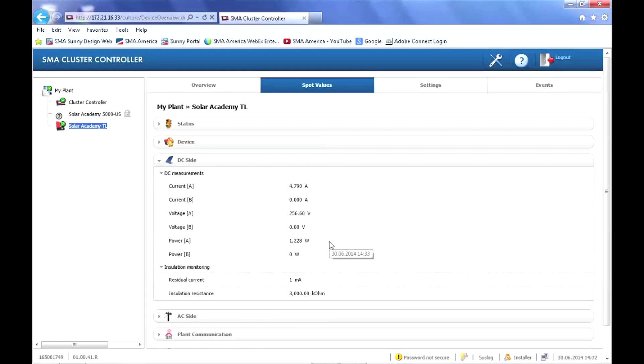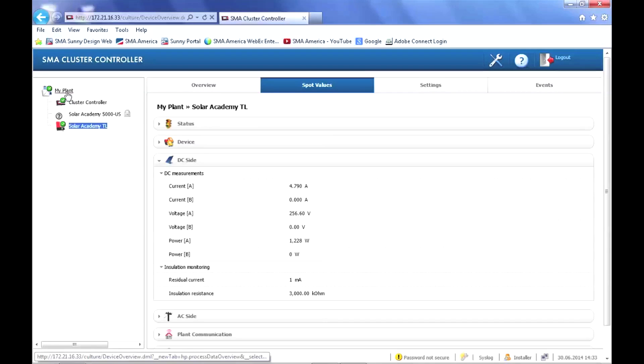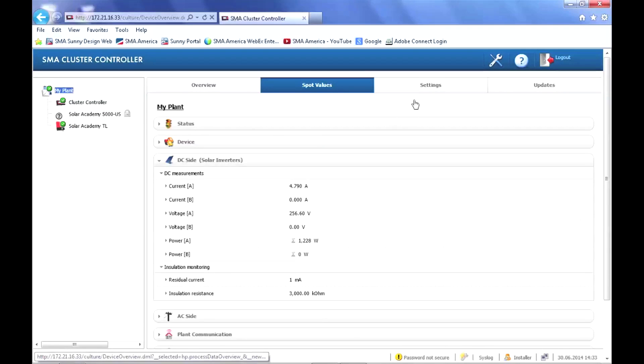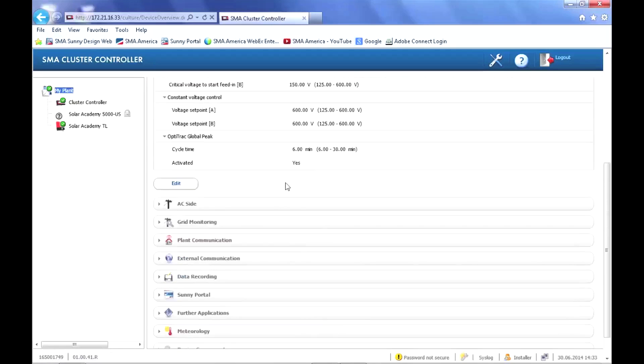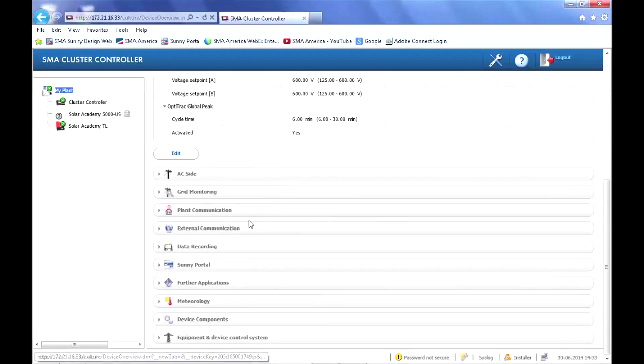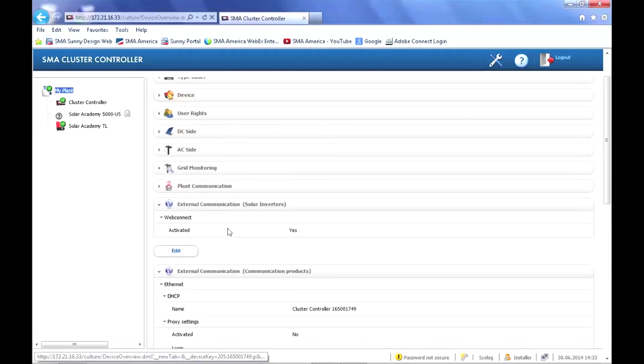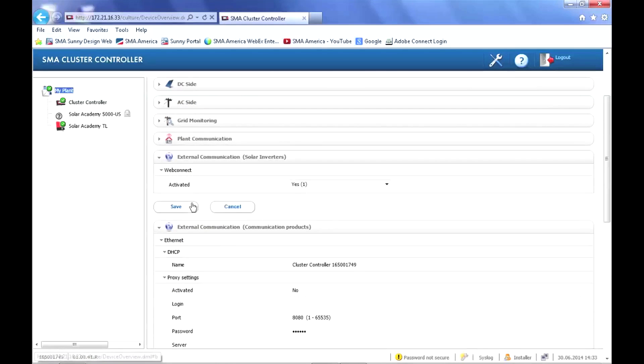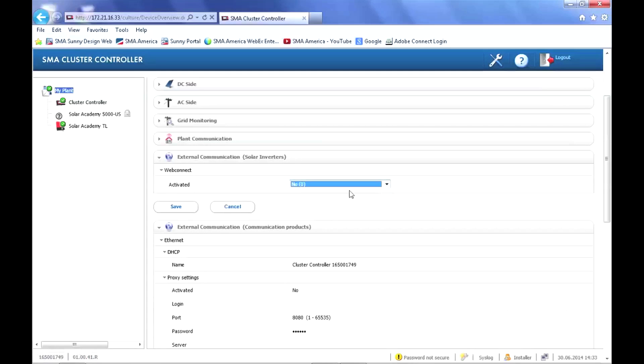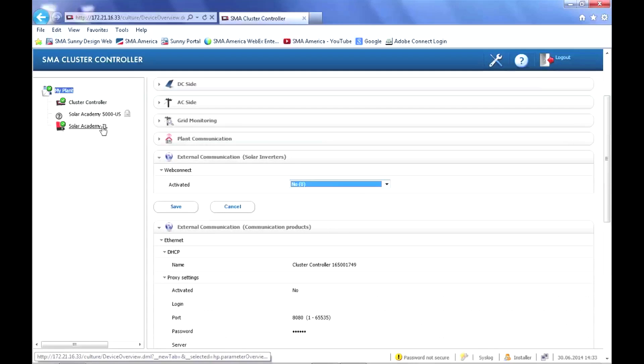One thing you will need to do is turn off the WebConnect function in the individual inverters. To do that, click on the plant in the plant tree, the settings tab, go down to external communication, and the first submenu will be WebConnect. Click edit to enable, choose no, and click save. And this will disable the WebConnect functionality so the inverters will not try to talk to the Sunny Portal. The cluster controller will do that.